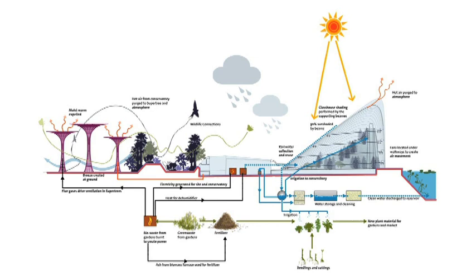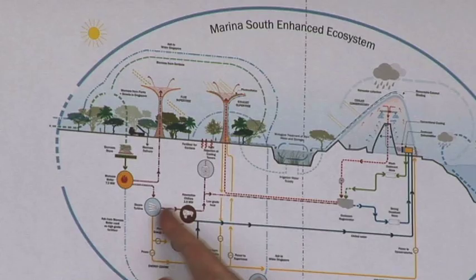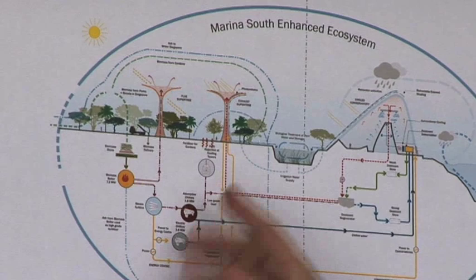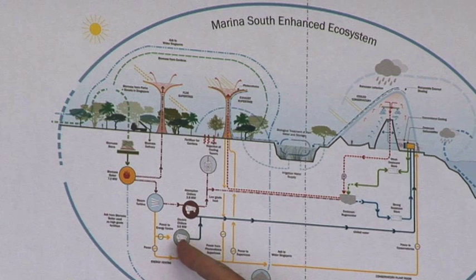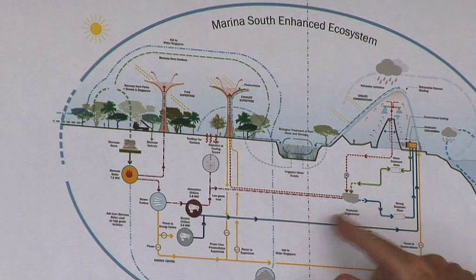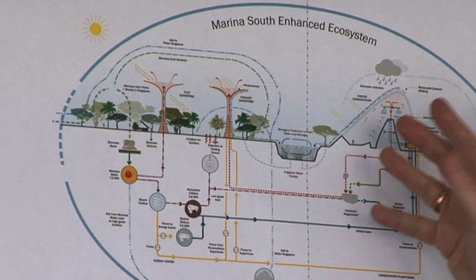It's a 7.5 megawatt boiler plant which generates steam, drives a turbine, and makes power. The waste heat from that turbine goes into two different chiller cycles. The absorption chiller — taking heat and generating cooling — is used to drive the conservatories. The secondary waste heat is then used as part of a desiccant process to regenerate desiccants which dry the air. We also take solar energy from the glasshouses — the heat that comes in and heats up the air at the top gets extracted and is also part of a desiccant regeneration process.